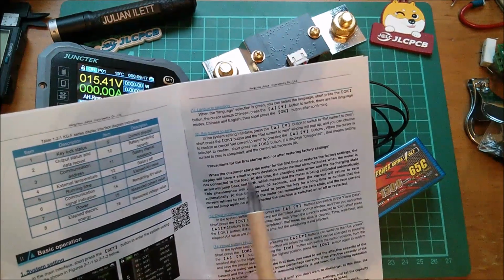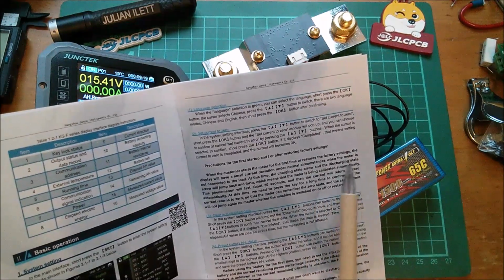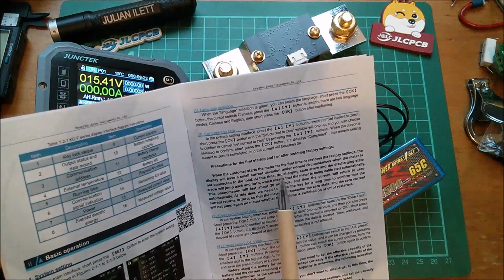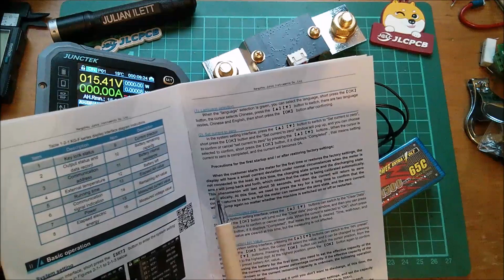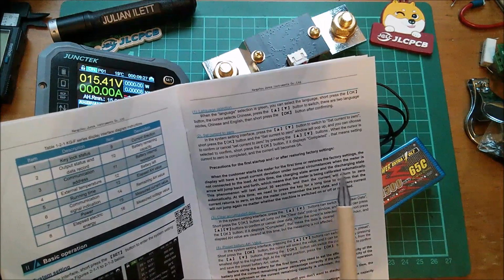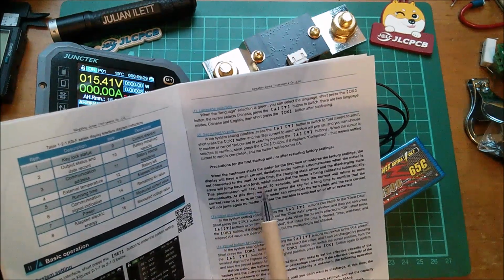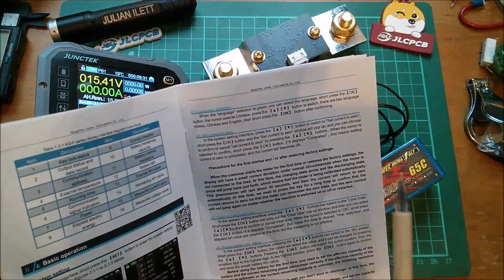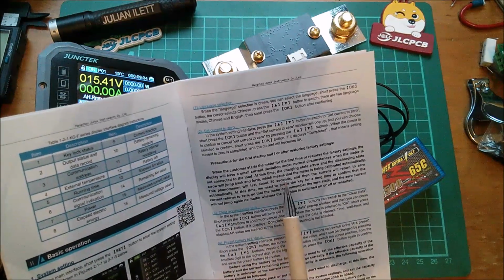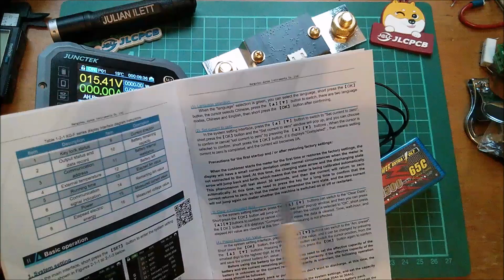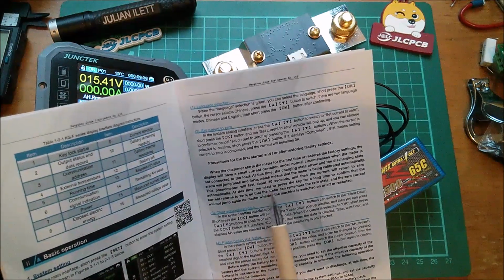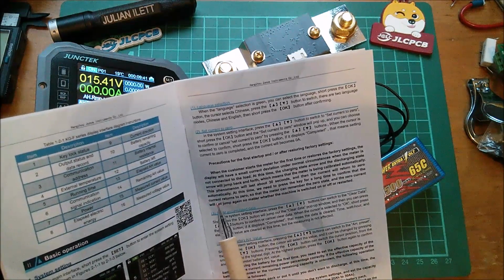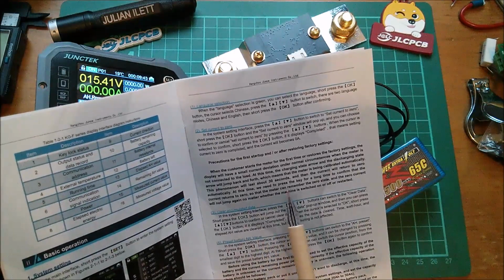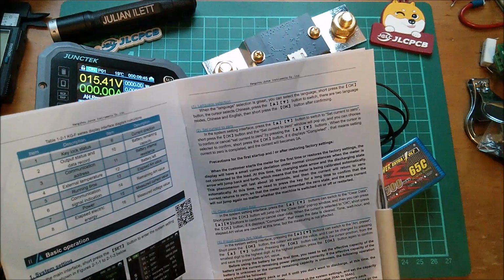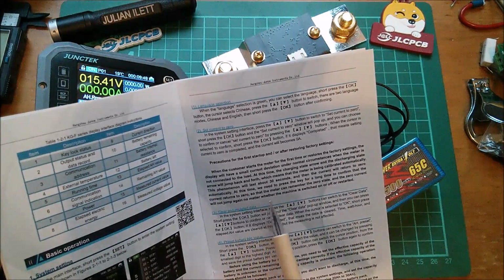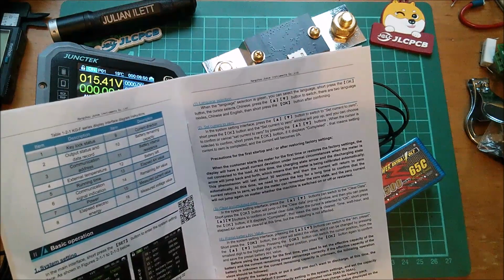This is interesting. When the customer starts the meter for the first time or restores the factory settings, the display will have a small current deviation under normal circumstances when the meter is not connected to the load. At this time, the charging state arrow and the discharging state arrow will jump back and forth, which means the meter is being calibrated automatically. This phenomenon will last about 30 seconds, and then the current will return to 0 automatically. At this time, we need to press the key for a long time to confirm that the current returns to 0 so that the meter can remember the 0 state, and the 0 current will not jump again no matter whether the machine is switched on or off or restarted.